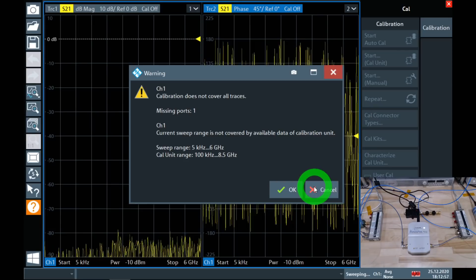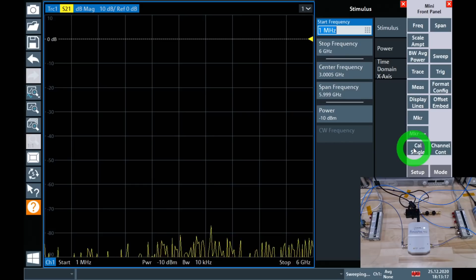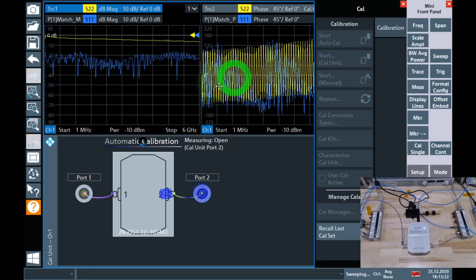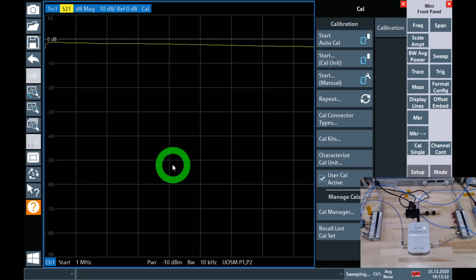The very first thing, we can go ahead and reach the frequency over here and then change that to 1 megahertz. We don't need to work that low frequency anyway. You can see that's already changed to 1 megahertz. I'm going to also go ahead and reconfigure the microwave switches, so we can reach the calibration unit. There we go. I just did that. And let's go ahead under the calibration menu one more time and perform an AutoCal. And you can see both of those errors are now gone and the calibration can be successfully performed. Once this is done, the instrument has the calibration at exactly the planes of the eCal unit, and I can go ahead and reconnect them back to the power amplifier.